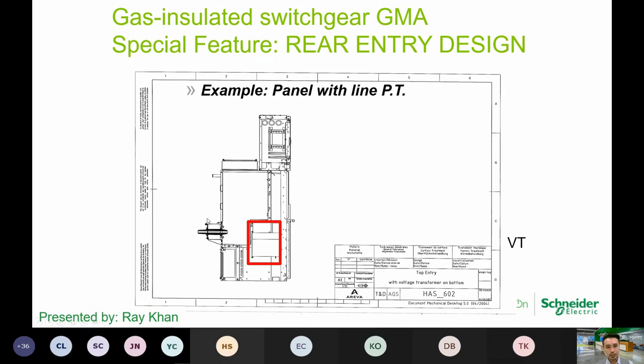All right, so the cable termination tools we use are very standard tools. They're using this deadbreak elbow connection, which is easier to terminate. And apart from this, the termination time is also much faster. Right. So over in here, you also see that there's a VT. So the VT is at the rear. We have it at the front and at the rear as well, depending on the user preference.